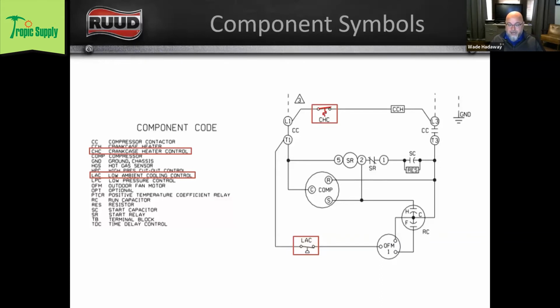So you can see as that line goes across, on the right-hand side, it's on the top of that contact. So as the temperature increases, that switch is going to be pushed open, right? So it's an open-on-rise temperature switch.